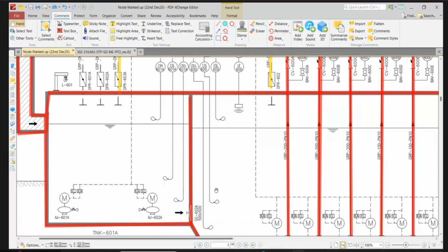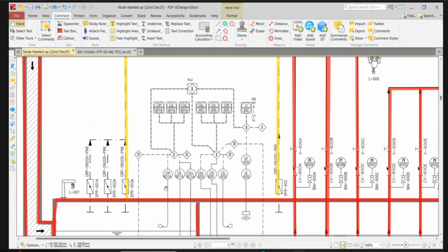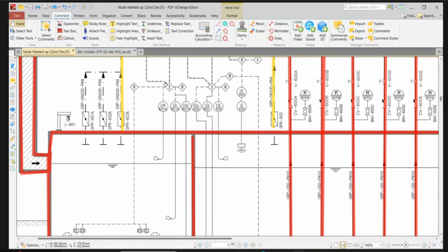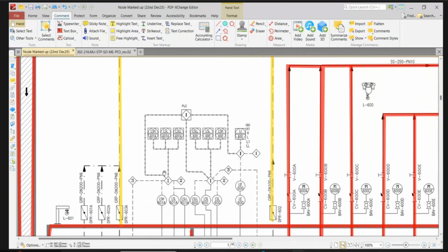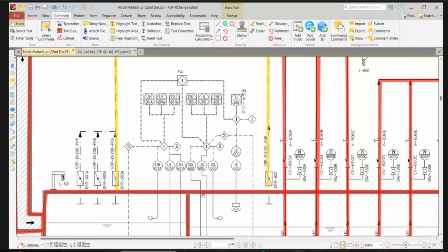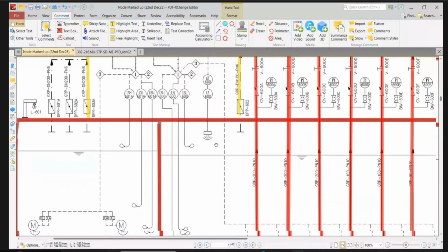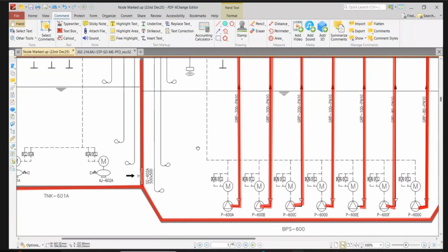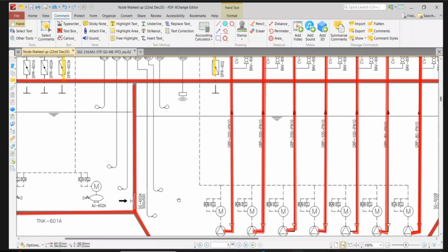We are going very slow. No, this one is controlled by maybe the operator. He can select by time. Like, no flow there, it will stop, right? Yes, yes. If there is no level inside the tank, it will stop. Right? Exactly. It will, for all pumps. Yes, for all pumps. If this pump trips, then a level will come into the picture.